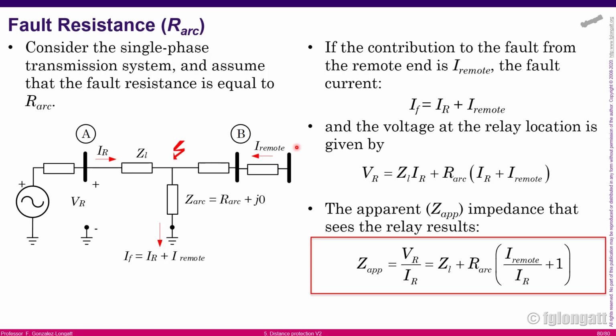What is happening there is, if we have a bolted short circuit, this impedance is zero. As a consequence, the voltage at this point is zero, and the current that the relay sees will be only the current given by dividing this voltage source by the sum of those impedances.